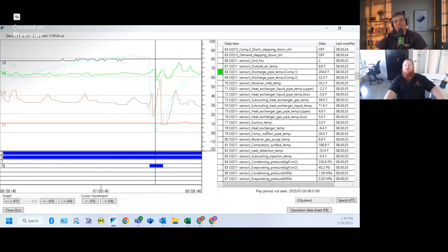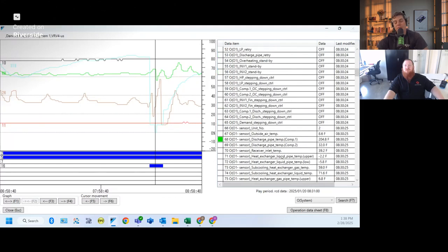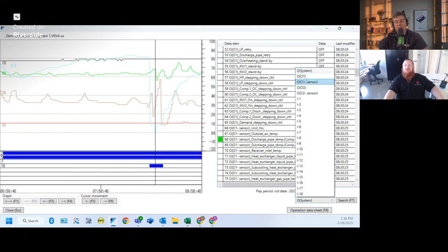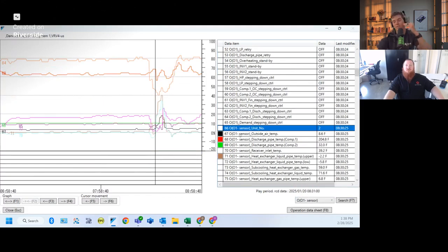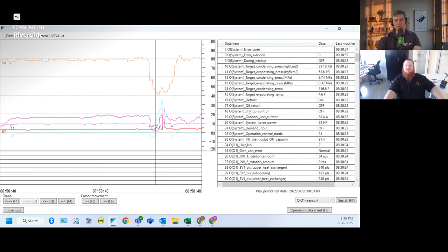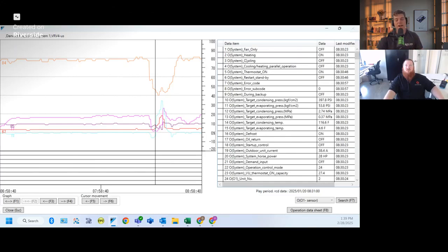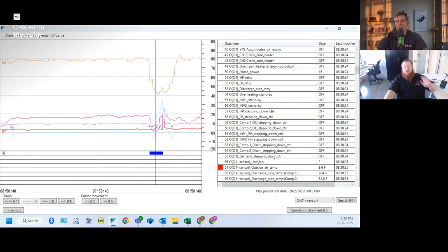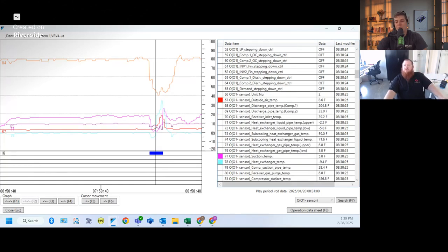And again, if a space is having difficulty maintaining temperature, say it's 50 degrees inside, or the space is 57, but the set point is 70 or 75, whatever it may be, the issue then becomes maybe the defrosts are so often and frequent that it doesn't run enough to deliver enough heating capacity at any given time to actually keep that space warm.